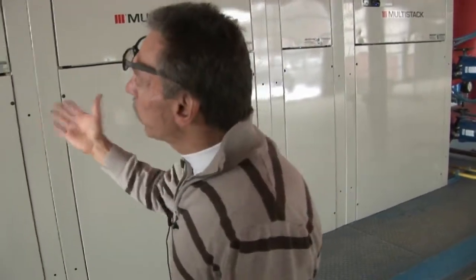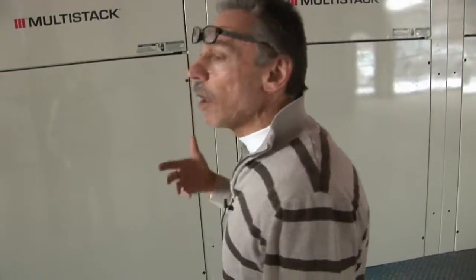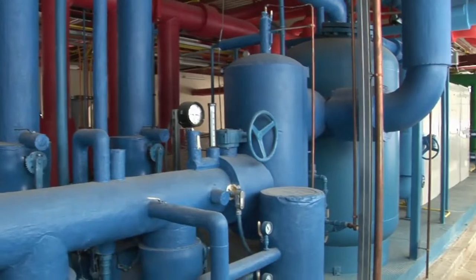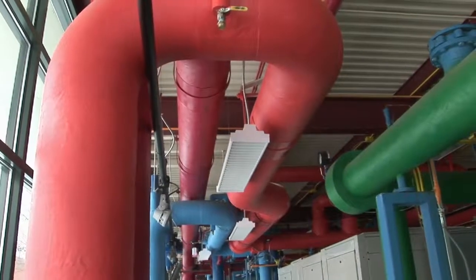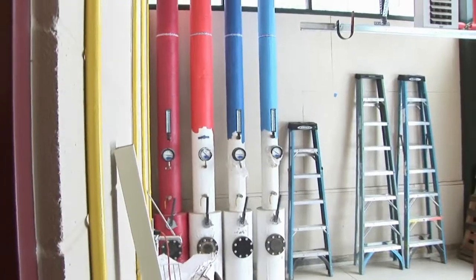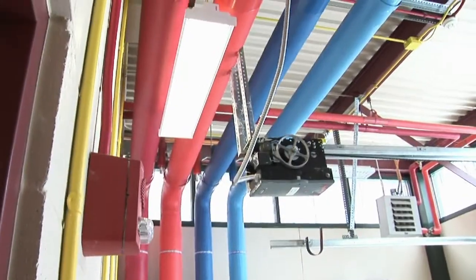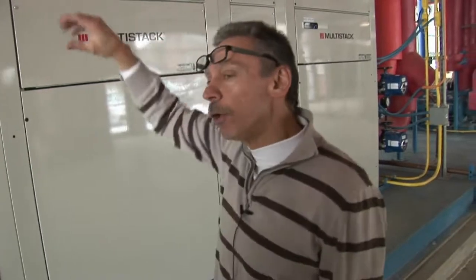So that's the great thing about this type of system, is you have that simultaneous heating and cooling modes that these can perform in. There's always going to be a cooling loop going out and back, and a heating loop going out to the buildings and back. But whether or not the building uses it depends on that building control system and those valves. So if a room needs more cooling, it'll open up a valve. That chilled water will start going through that fan coil unit in that room. And that's what you have, is in each building you have distributed fan coils for the various zones in that building. Currently we have 3 buildings served by this central plant.